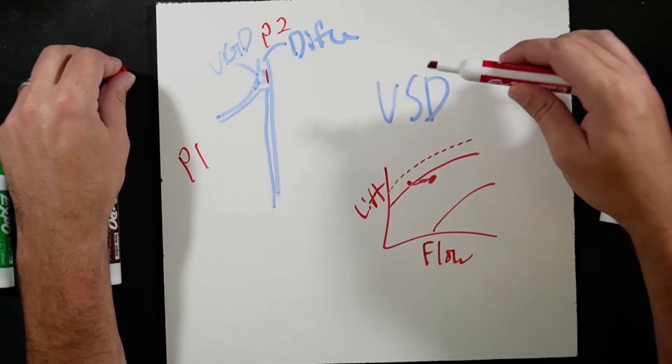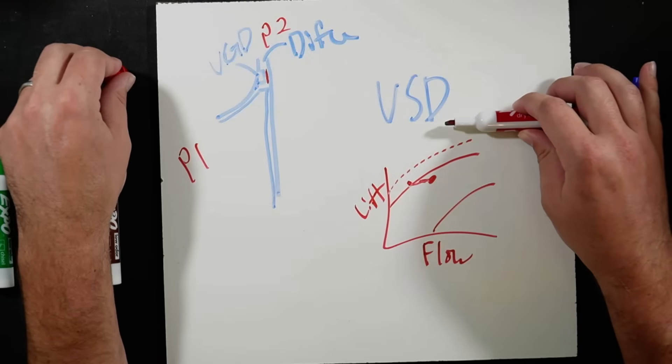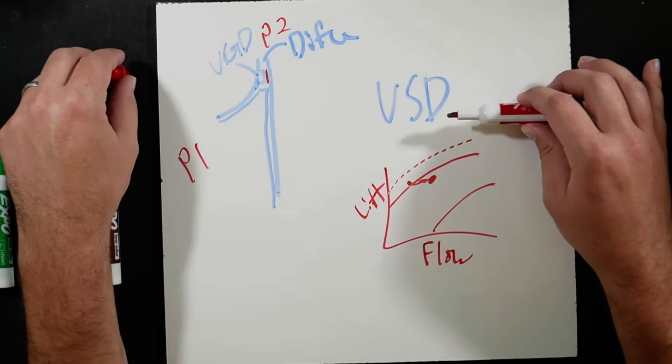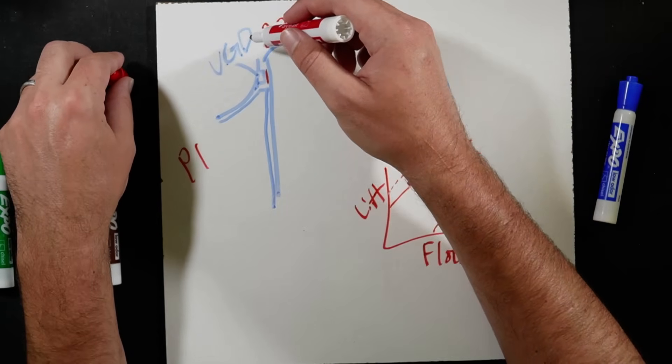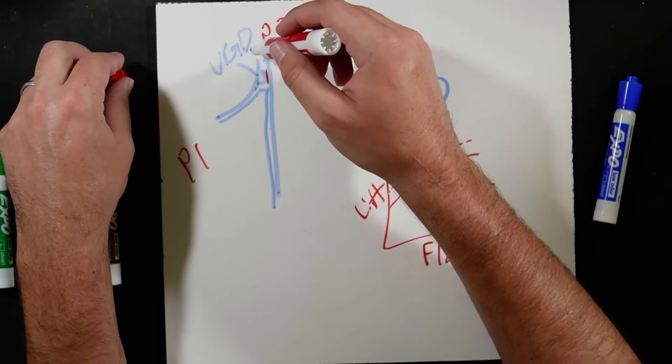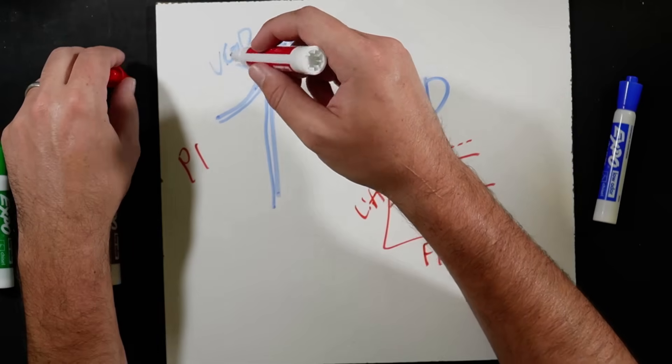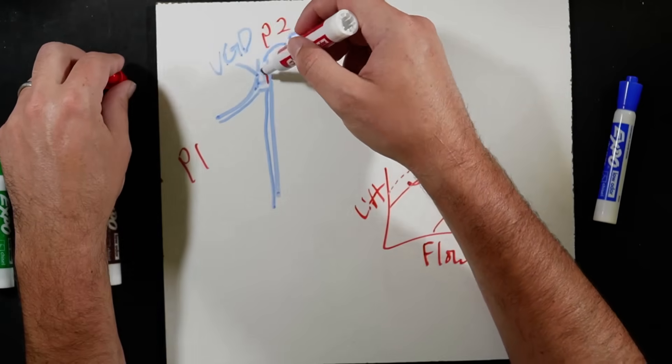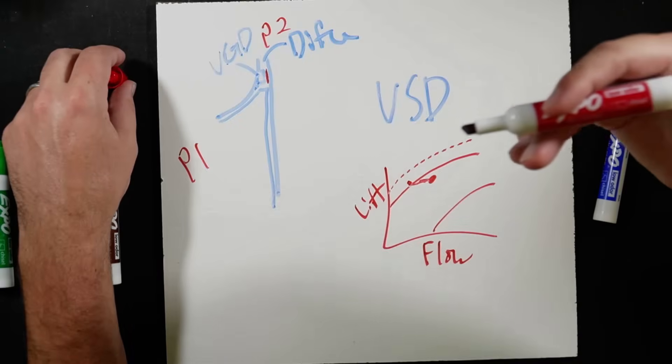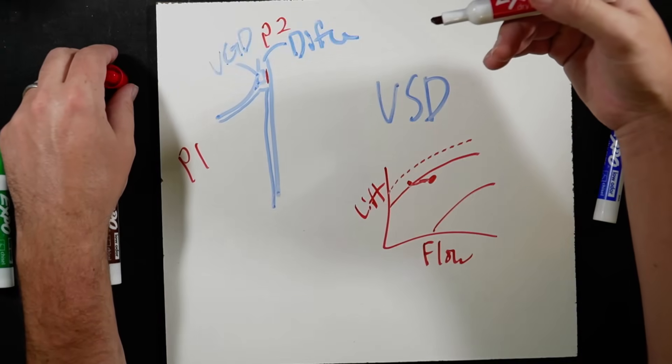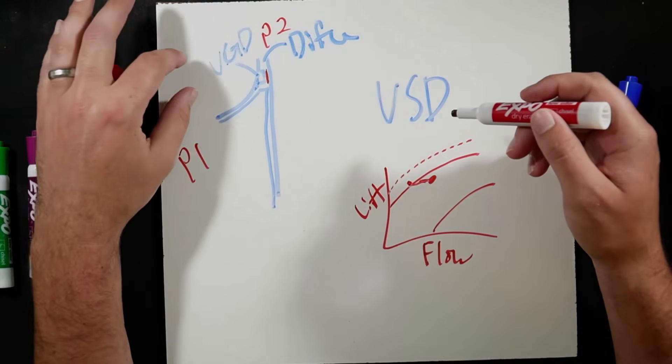But once the compressor actually hits its minimum reference speed that it can get to, then the compressor will intentionally use this VGD, not just for surge protection, but also for unloading the compressor further by restricting this diffuser gap and allowing less total volume through. So it serves a dual function at that point with what it's doing.